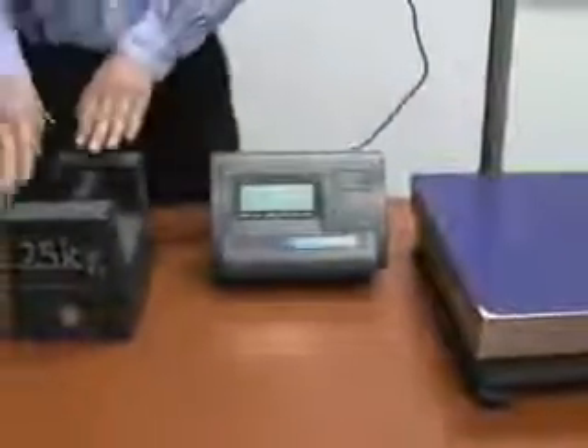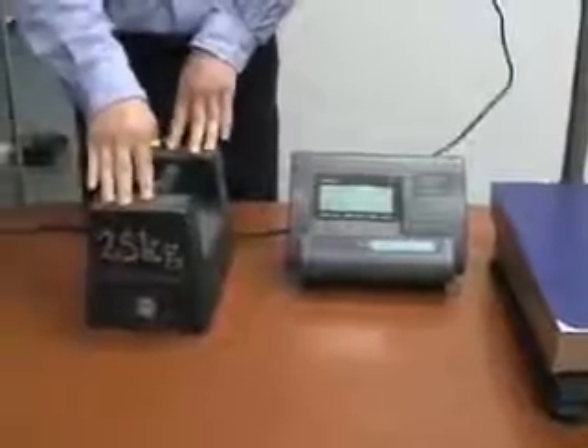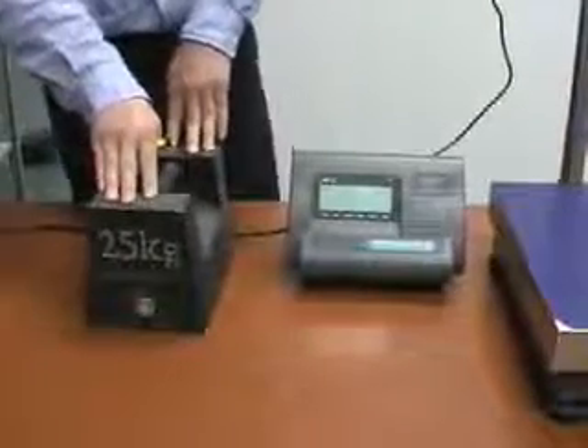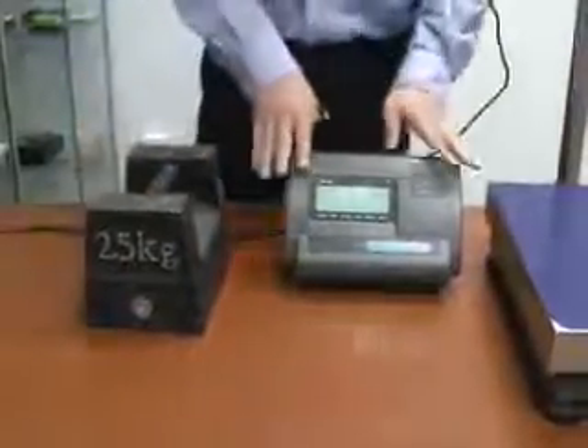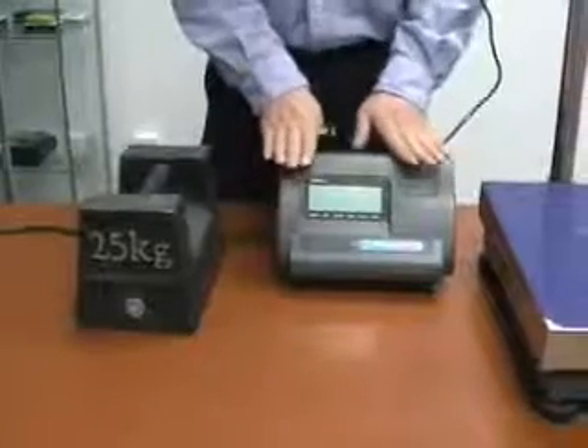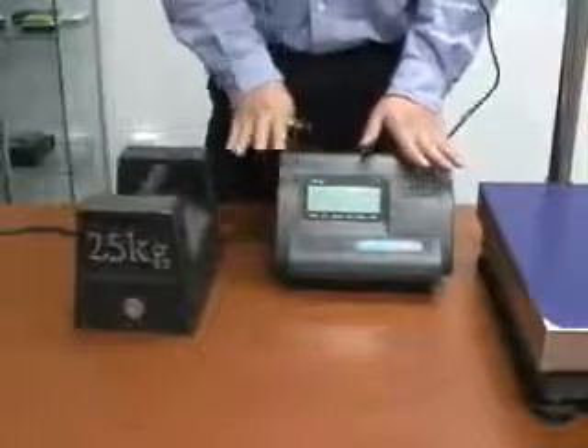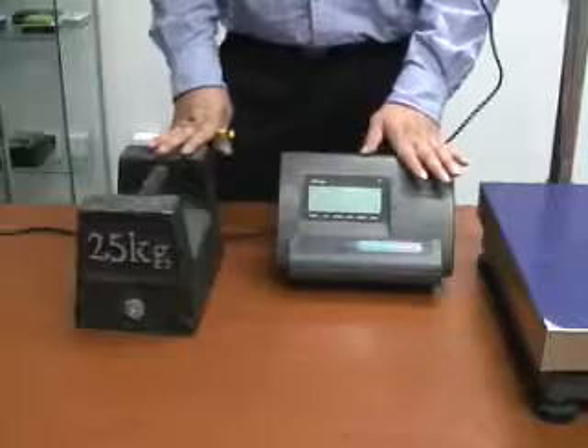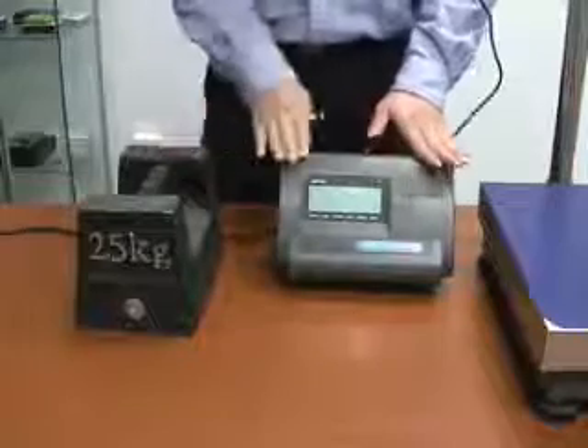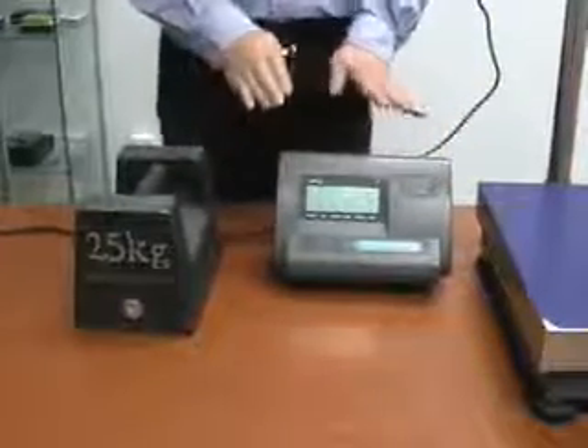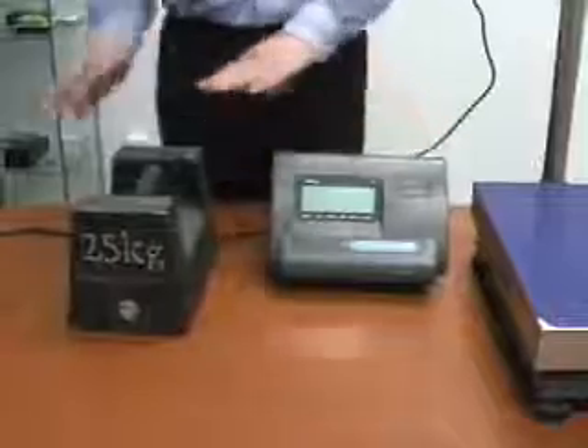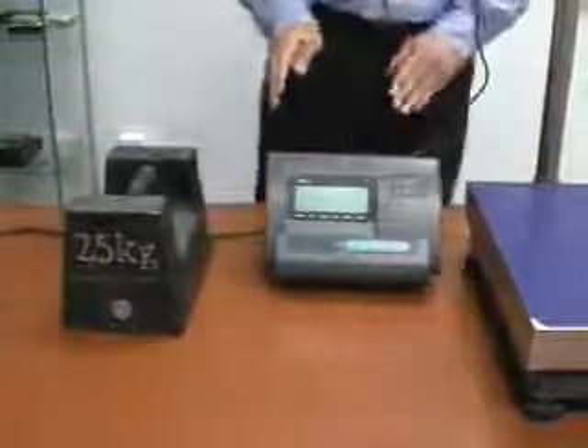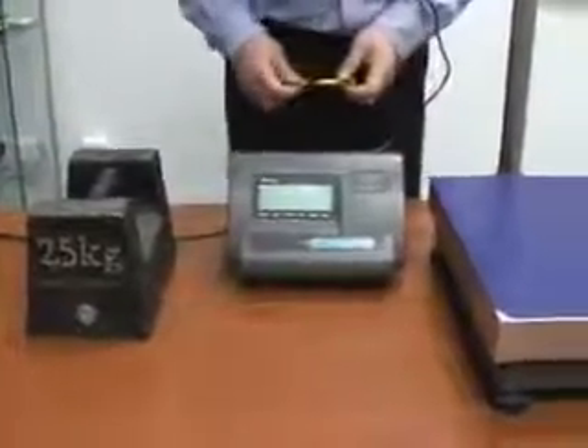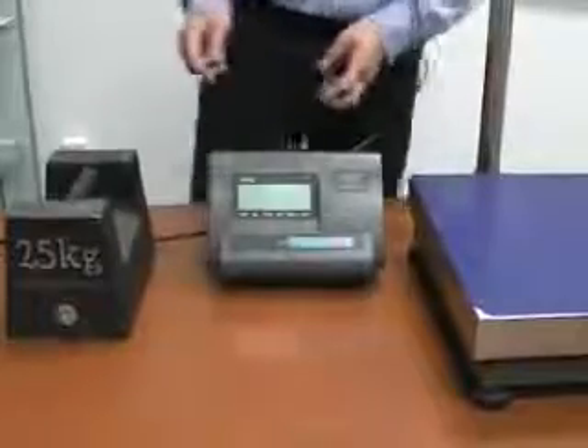And also we need a calibration weight. For example, here we have 25 kg. Please note that this indicator can only be calibrated with a kg calibration weight. It doesn't work with pounds for the calibration. Though the scale can show pounds after the calibration, that's another issue. Now we can show you how to calibrate the scale.